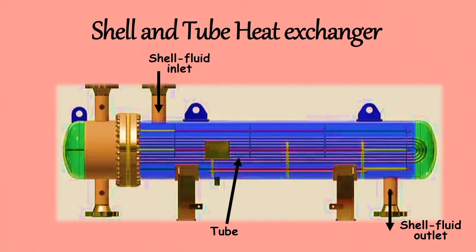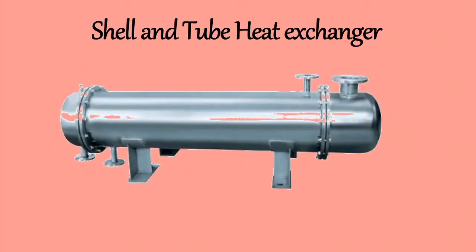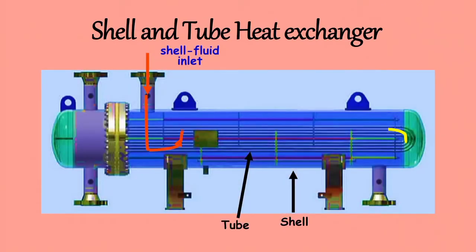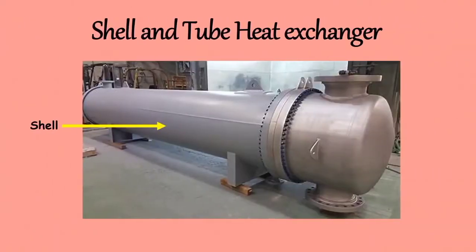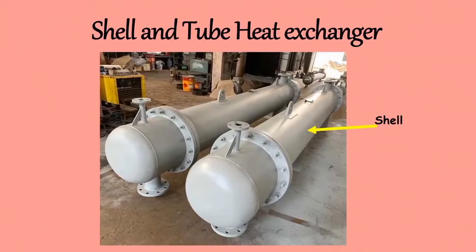The first component is the Shell. The shell is the outer covering of the heat exchanger. It is usually a cylindrical casing through which one of the fluids flows in one or more passes. It is commonly made up of carbon steel. It may be cut to the required length from a standard pipe up to 60 cm diameter, or fabricated from plates. The minimum thickness of a shell made of carbon steel varies from 5 mm to 11 mm, depending upon the diameter.